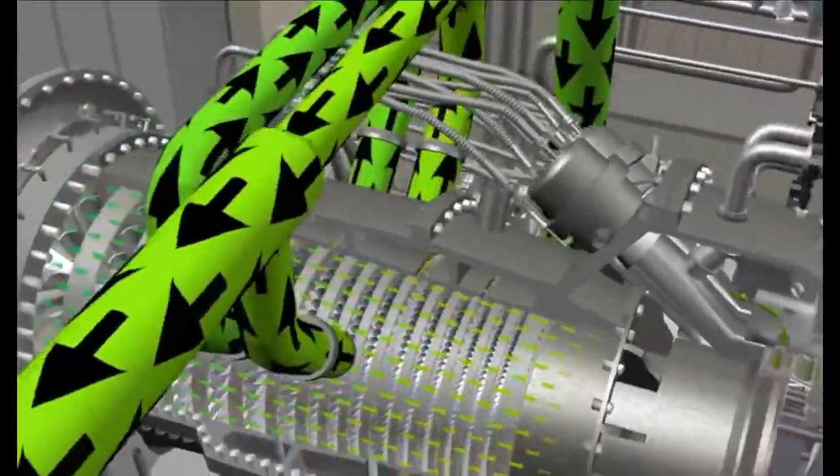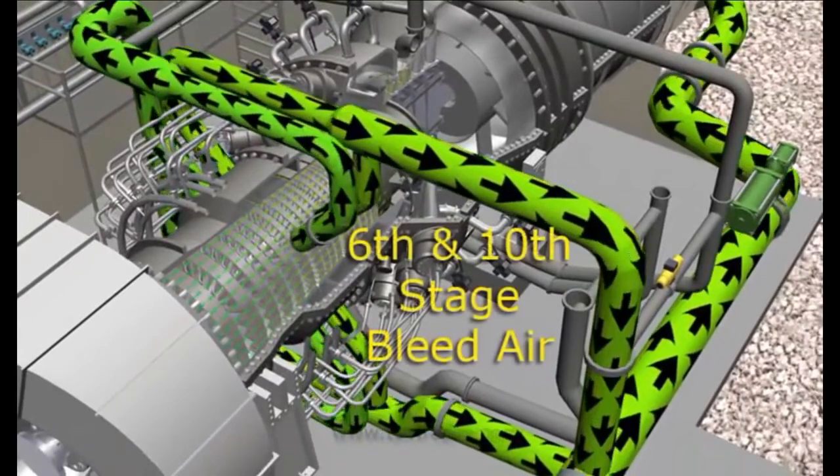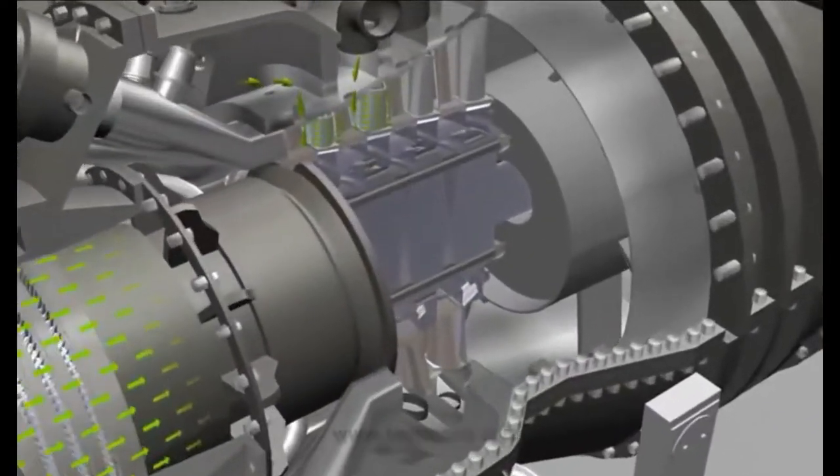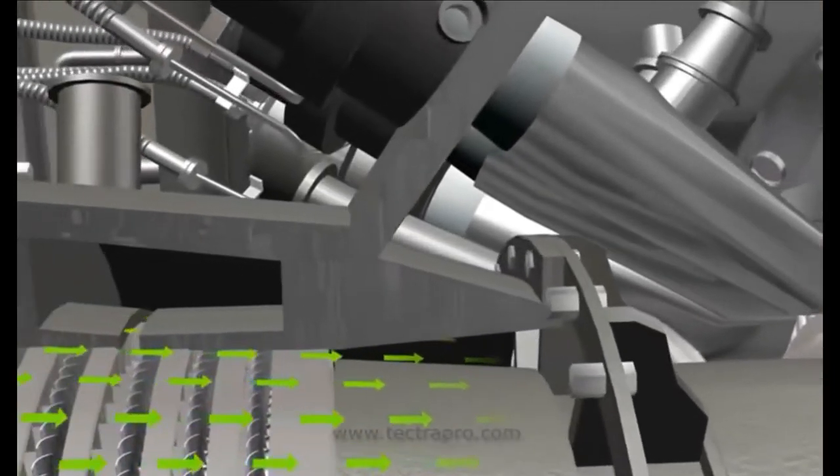After the rotor has accelerated to a speed where surging is no longer a concern, the sixth and tenth stages of compressor air bleed to the turbine exhaust is closed. From this point, sixth and tenth stage bleed air is directed to cool the last stage stationary blades of the power turbine.